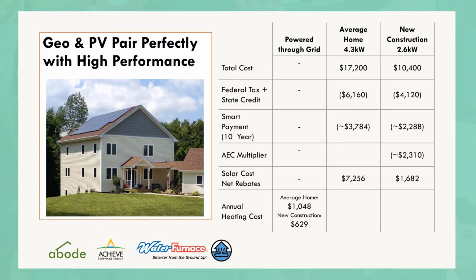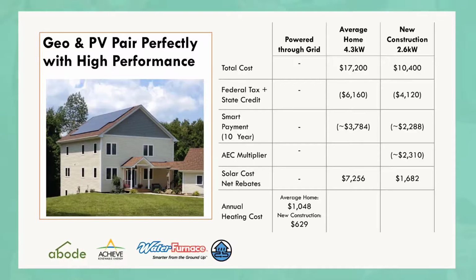All right, this chart talks about different scenarios interfacing a ground source system with a PV system. In the first column, powering the system through the grid. So for an average type house, there's no additional cost beyond the geothermal install, because you're not putting in solar. And in the model that was run here, the heating of that average home with the geothermal system was around $1,050 for the year. And in a new construction scenario, that would be lower because the new construction would be a tighter home. In that average home, to offset the operation of the ground source system, you need about 4.3 kilowatts of solar array, which at current rates is about $17,000.